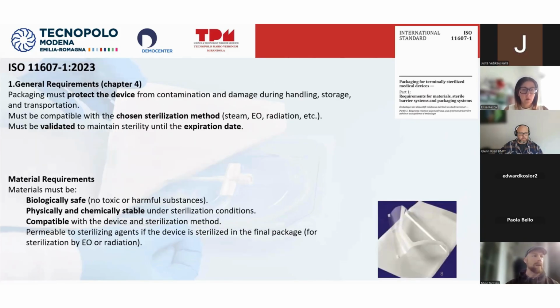So what are the general requirements? The packaging must protect the device from contamination and damage during handling, storage, and transportation. It must be compatible with the chosen sterilization method, for example steam, EO, radiation, etc., and must be validated to maintain sterility until the expiry date.